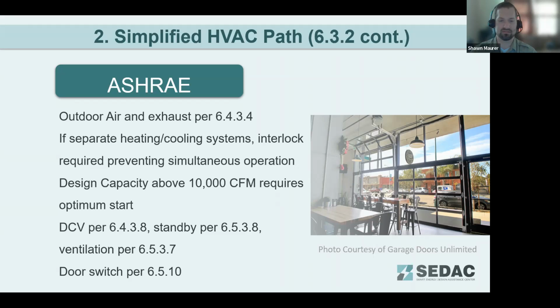If the doors are open, the HVAC system is going to be triggered to off or to some kind of neutral conditioning temperature where it's not trying to meet full conditioning requirements, minimizing its energy consumption and just doing kind of the bare minimum to meet what the space still needs for ventilation purposes.